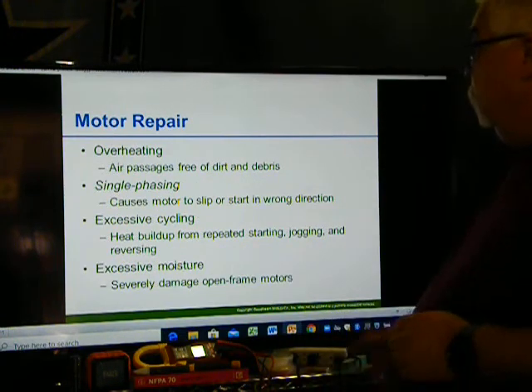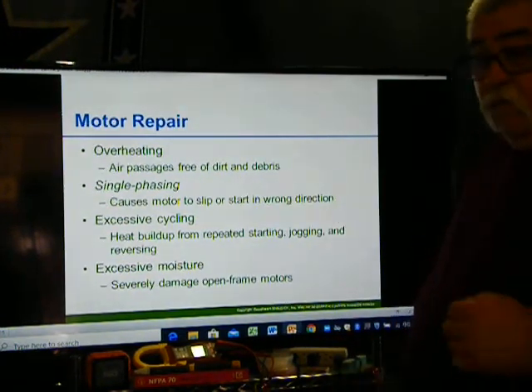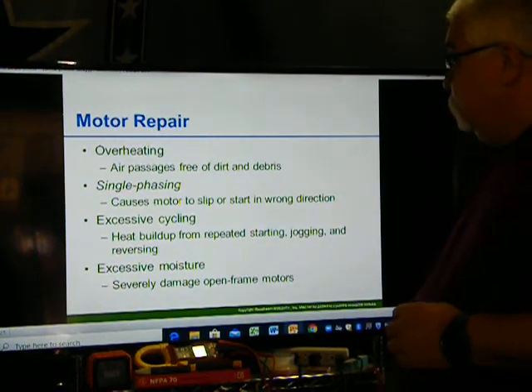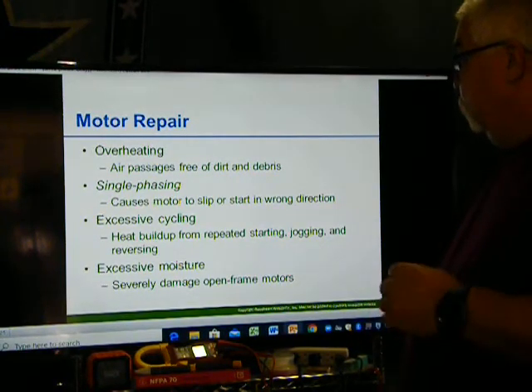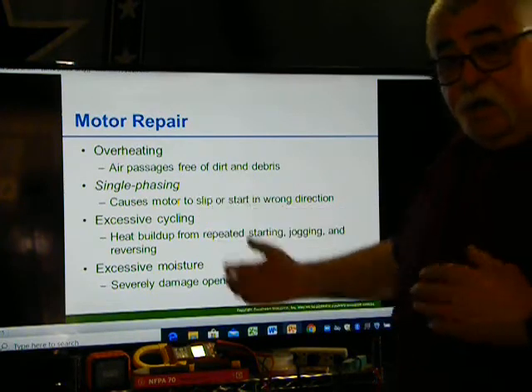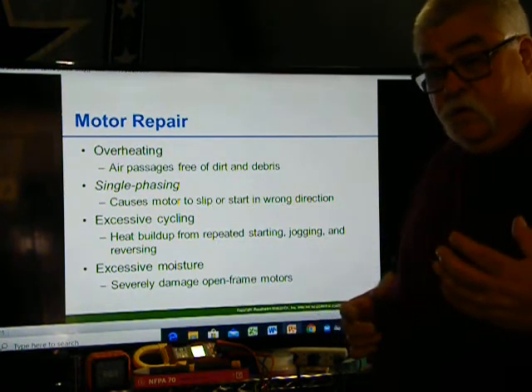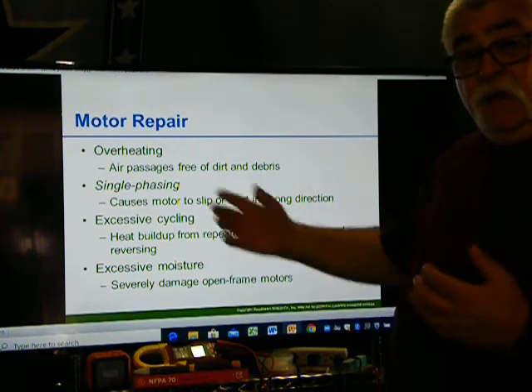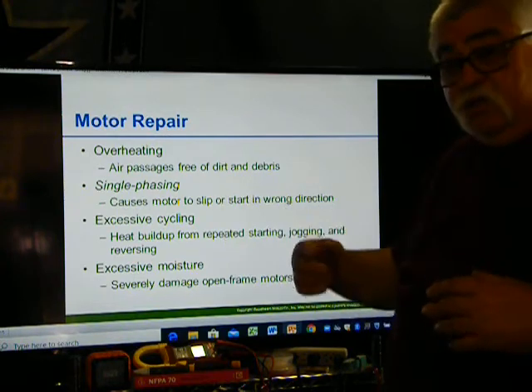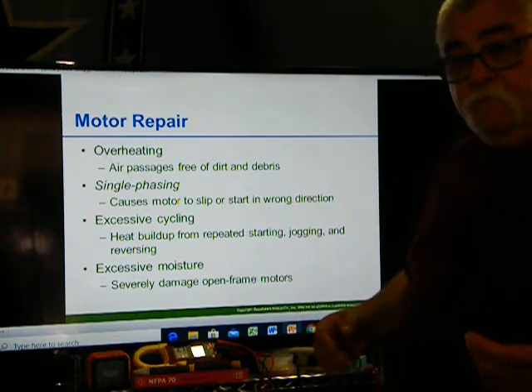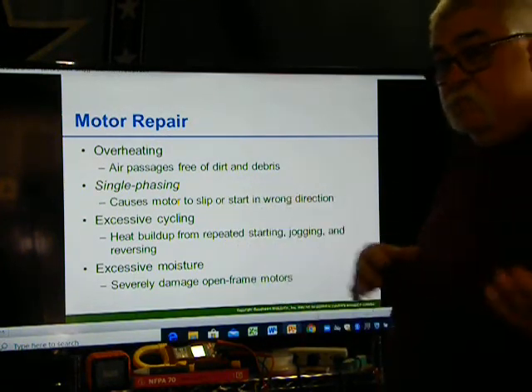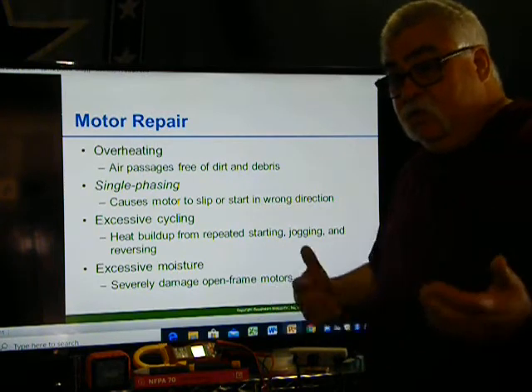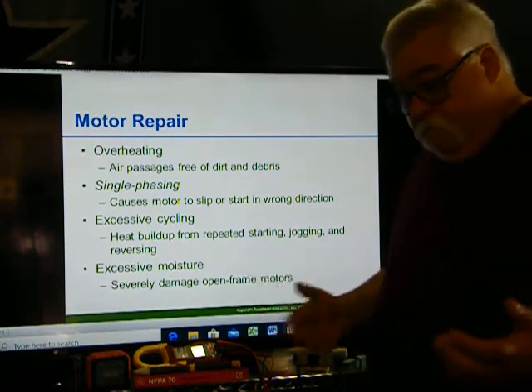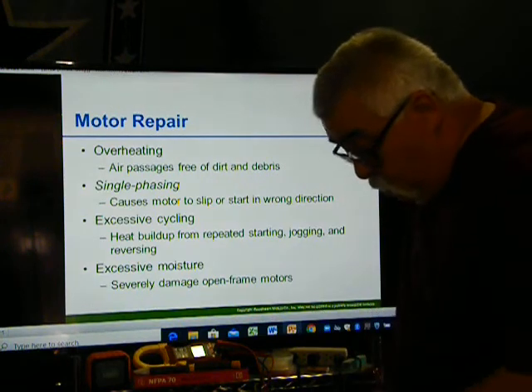Overheating. Another cause of overheating is that the air passages need to be free of dirt and debris, so the motor's got to allow air in and out. That's why some of the motors are open. It's got fins on it to blow air to cool itself down. So you have to allow air to move through it to keep the motor within what it's designed to handle. You want to make sure nothing causes it.